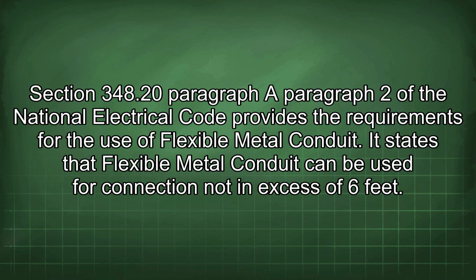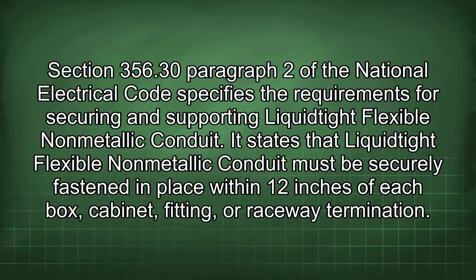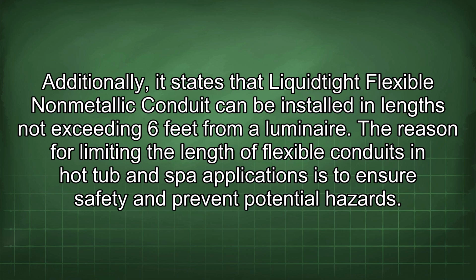Section 348.20 Paragraph 2 of the National Electrical Code provides the requirements for the use of flexible metal conduit. It states that flexible metal conduit can be used for connection not in excess of 6 feet. Section 356.30 Paragraph 2 of the National Electrical Code specifies the requirements for securing and supporting liquidtight flexible nonmetallic conduit. It states that liquidtight flexible nonmetallic conduit must be securely fastened in place within 12 inches of each box, cabinet, fitting, or raceway termination.